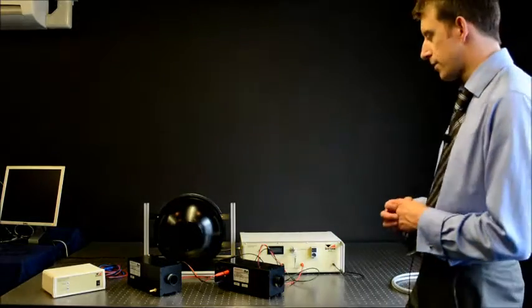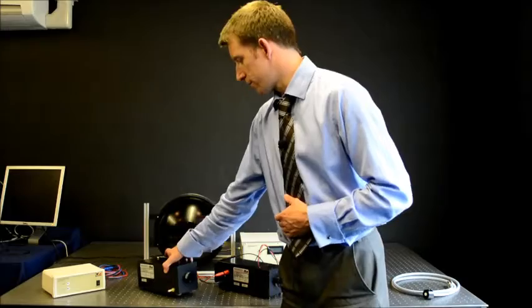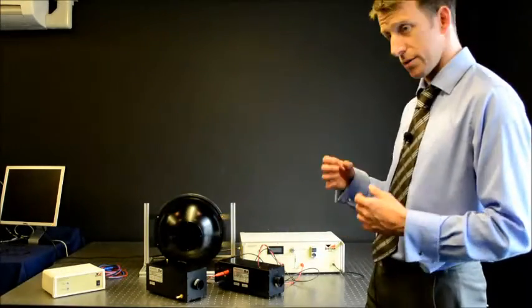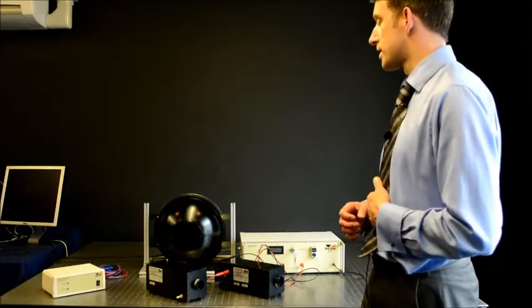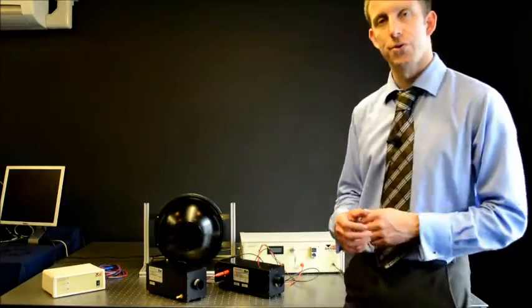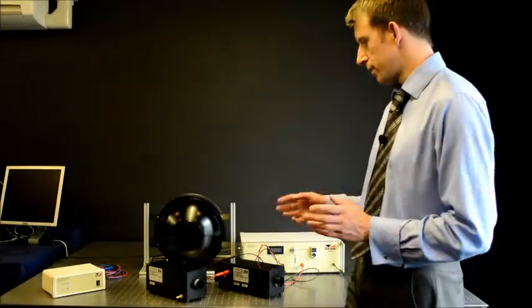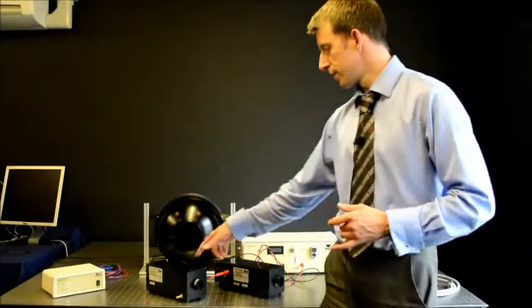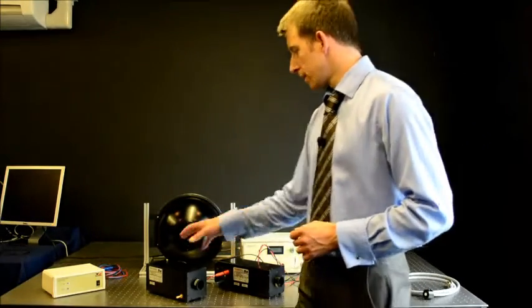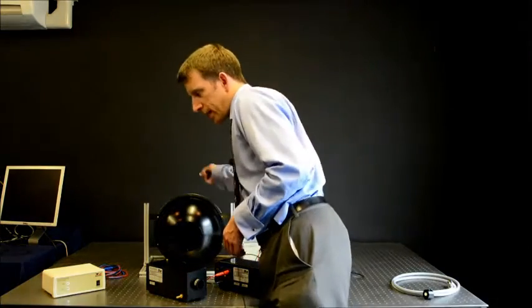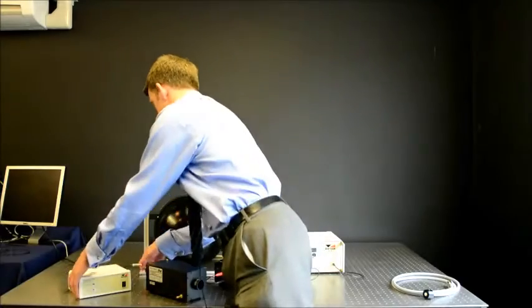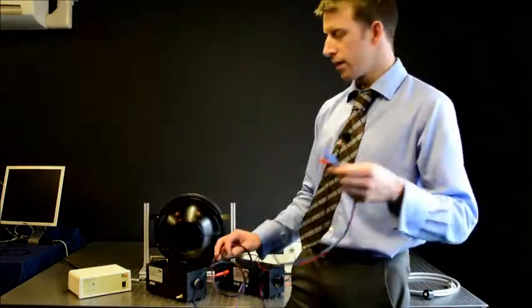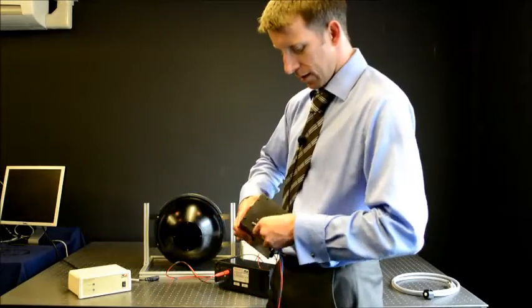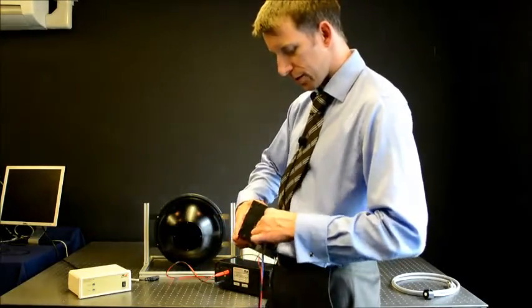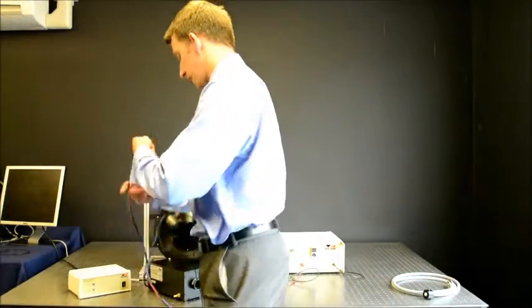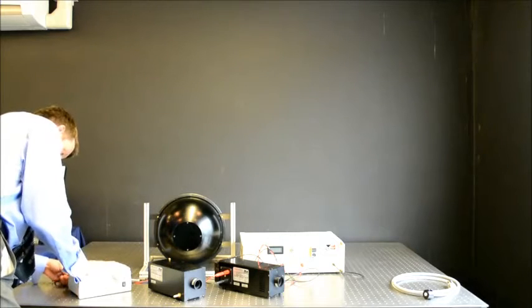The other standard of spectral irradiance is the CL7 deuterium standard. This is based on a deuterium lamp, a short arc lamp, which has high UV emission from 200 to the vicinity of 400 nanometers. The overlap region between 300 and 400 being used to associate the two calibrations. The CL7 is operated from its own dedicated power supply, the 706, and requires 3 connections: anode, cathode and heater connections, which we will connect to the rear of the 706.